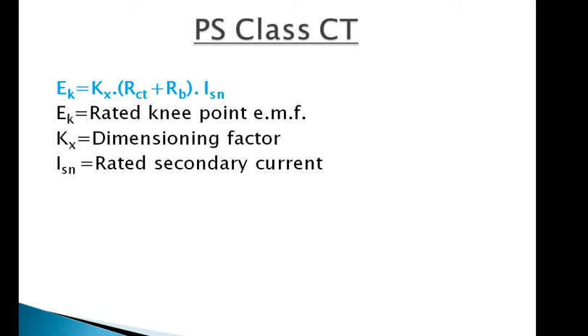IEC defines the PS class CT dimensioning as per the equation: E_k = K_x × (R_ct + R_b) × I_sn, where E_k is the rated knee point EMF available in the CT manufacturer's catalog, K_x is the dimensioning factor, and I_sn is the rated secondary current. If the above criteria are fulfilled, then the PS class CT is OK for protection CT sizing calculation as per IEC method.